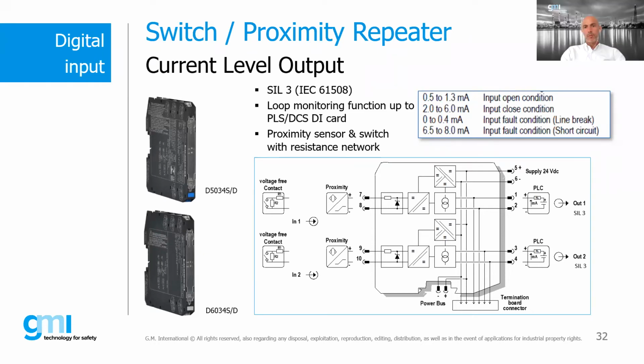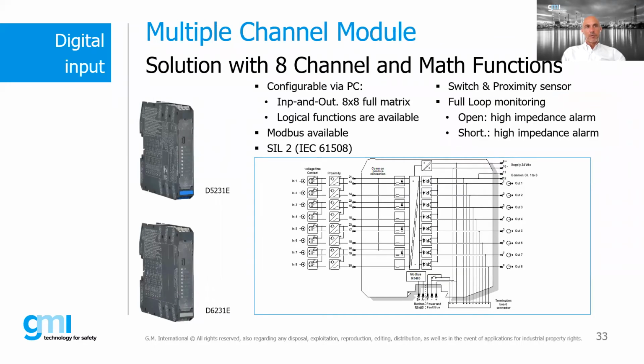So for input open or closed in this case, there are specific current values. When you have a fault, in this case line break or short circuit, the current is of course equal to 0, or something like that, between 0 and 0.4 milliamp. And we have a high current between 6.5 and 8 milliamp that simulates the short circuit. This is the proximity level current.